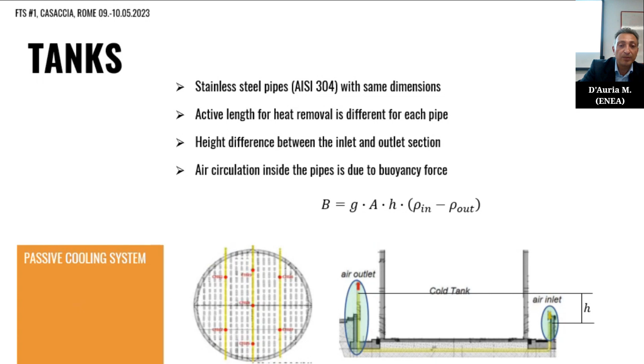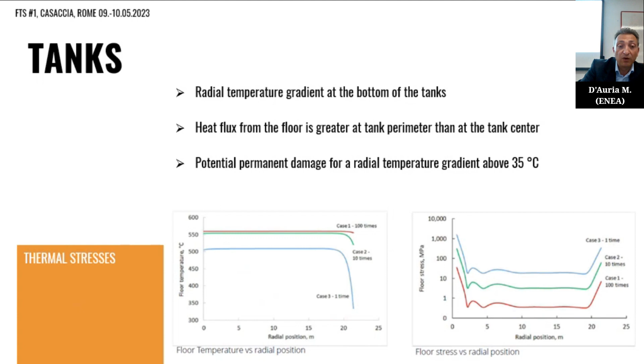Another issue at the floor of the tanks is thermal stresses, because near the center of the tank, the thermal resistance to heat transfer from the floor to the foundation can be greater than the thermal resistance at the perimeter of the tank. So the heat flux from the floor is greater at the perimeter than at the tank center. Simulations show that any radial gradient above 35 degrees is sufficient to permanently damage the floor.